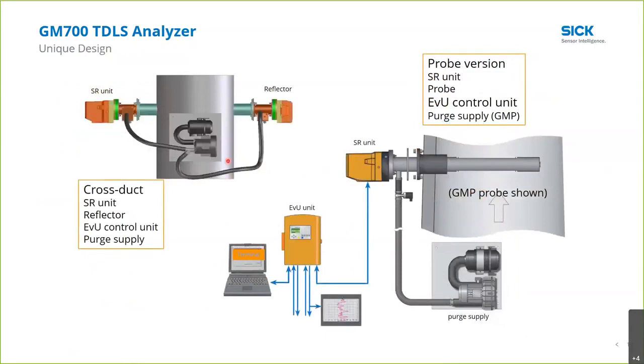Here are the typical configurations. This is a cross duct unit with a blower. If you have any amount of high pressure, we'll need 2 blowers in this application. And here's the GMP probe, which is typical for ammonia using the GMP. We will have a blower as well, and that blower can be certified for Class 1 Division 2 also. In both cases, the analyzer head is connected to a remote set of electronics. It's called an evaluation unit, and this is where your I/O is handled, and it has a local display on it, and you can do configuration with a laptop computer or do communications to your DCS if you're not using analogs.